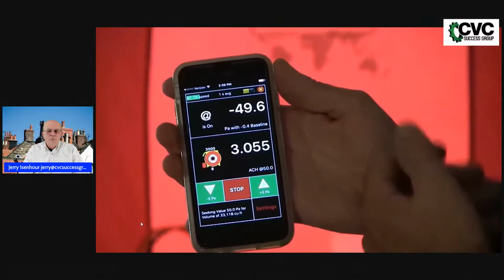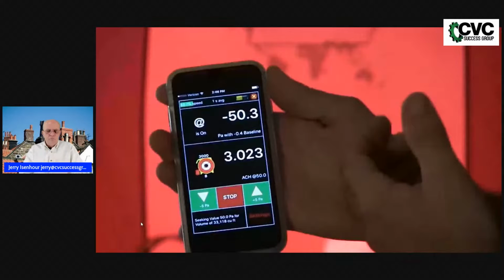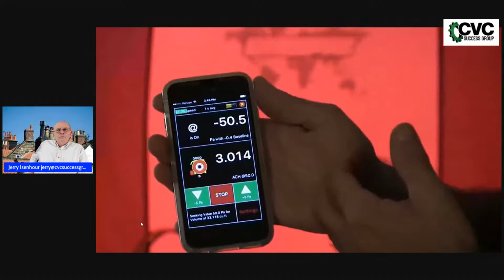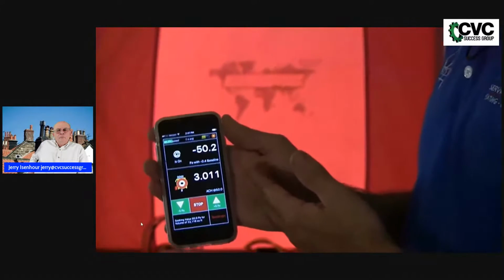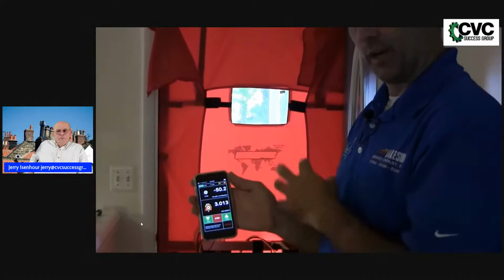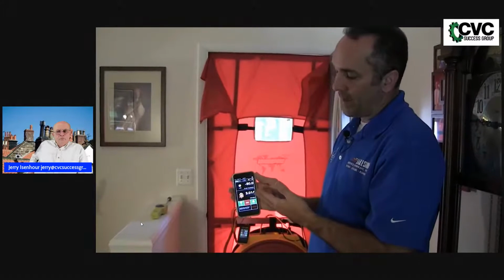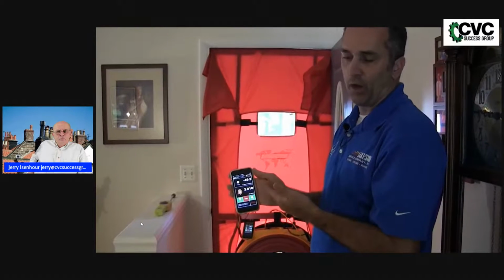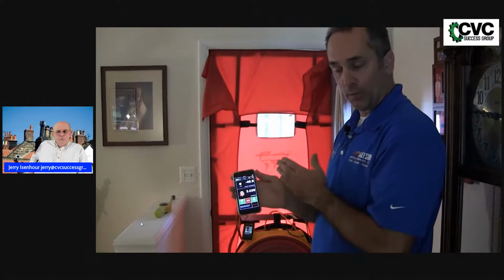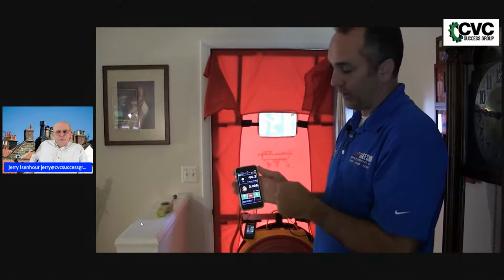And for new construction, they're looking to get 4 to 5 air changes per hour in the new home for the 2015 IECC National Energy Code. So this house is actually really tight. We might talk about an ERV or HRV so that they can bring in more fresh air. A lot of houses that haven't had work done on them may say anywhere from 8 to 12 or even as high as 20 air changes per hour. So the higher the number, the higher the blood pressure. So this is a really great illustration on how many air changes per hour is possible in a house.